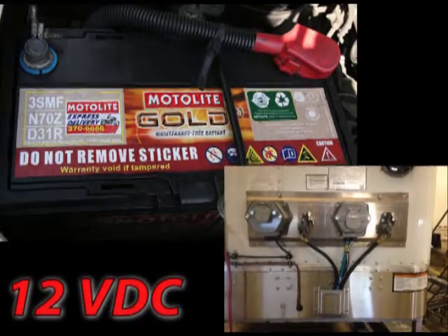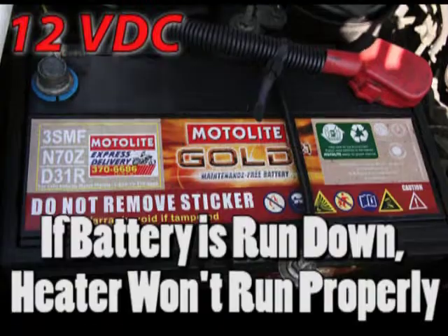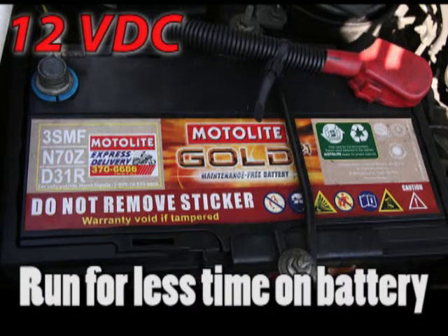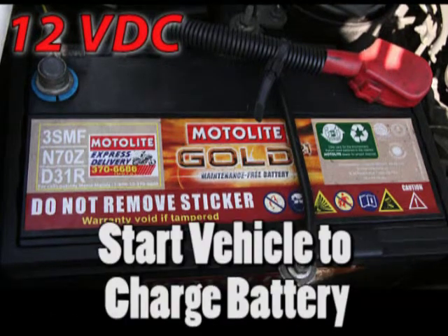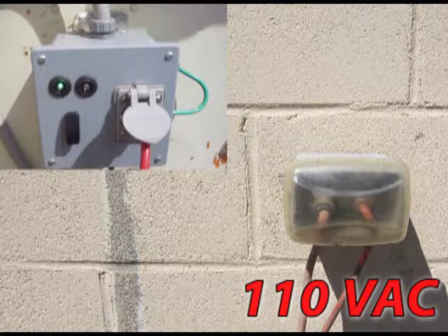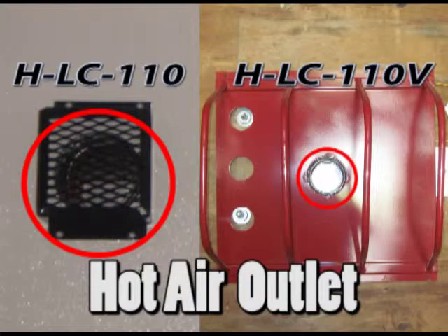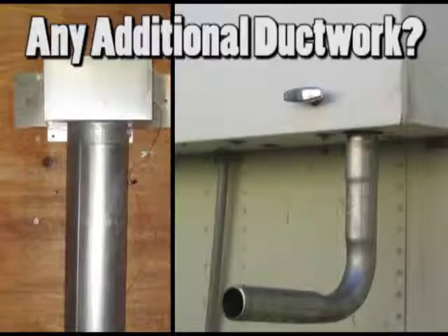Check if the heater is running off the vehicle battery only, with the vehicle not running. If the battery is significantly run down, the heater cannot receive enough voltage to operate properly. Running the heater for less time on battery or starting the vehicle should correct the problem. Check if the heater is running off of 110 volts AC shore power. Check that none of the inlets or outlets to the heater are blocked or any ductwork is damaged.